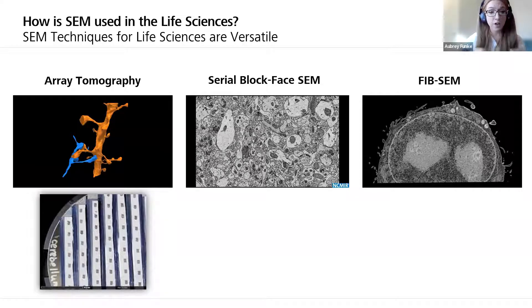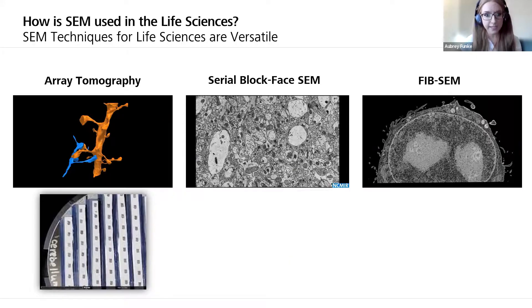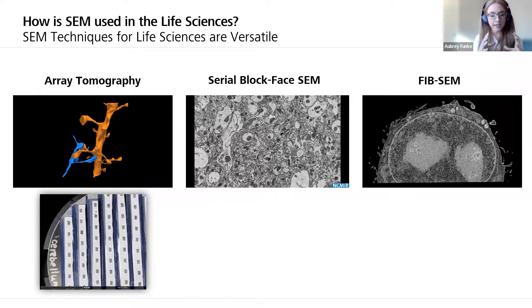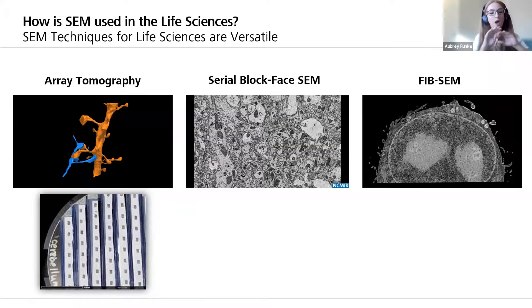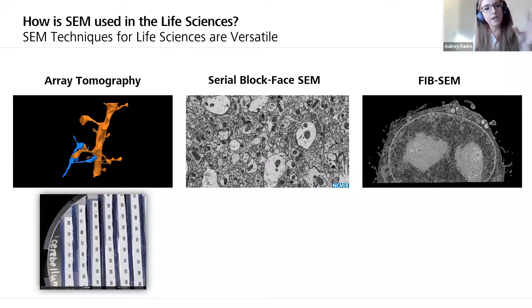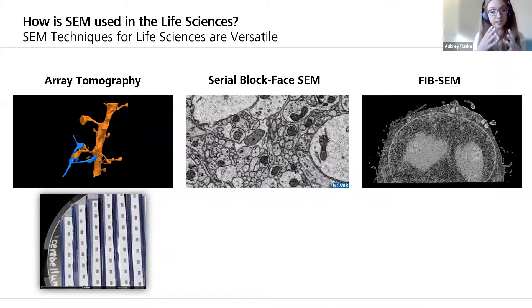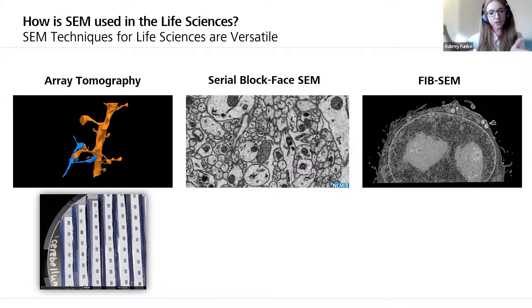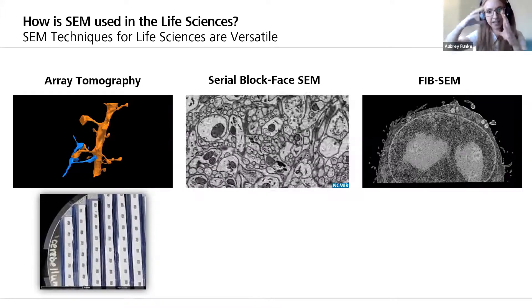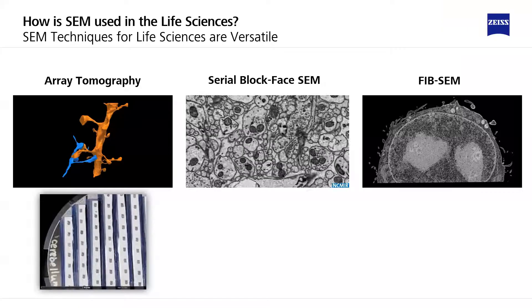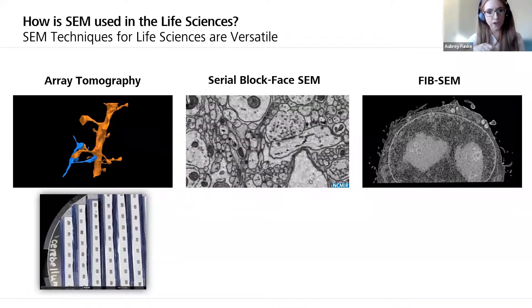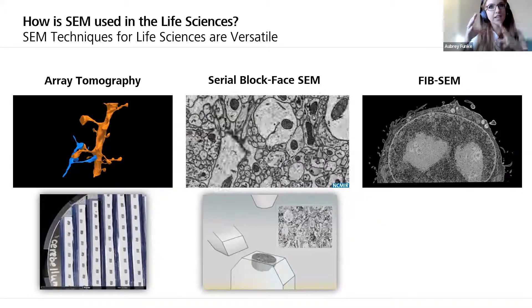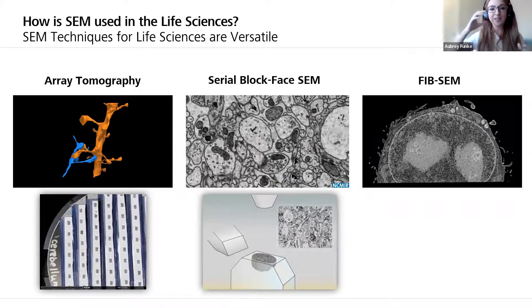Another volume SEM technique is serial block face SEM, or SBF-SEM. This is direct imaging of a sample block that's been resin embedded in some type of epoxy or plastic. The SEM has an in-situ ultra-microtome that takes really thin slices of that sample, then the scanning electron beam scans the surface and gives us an image. We cut away the top, scan the surface, and get an image, doing that over and over to create volume data — saving the time it takes to use the ultra-microtome and collect all those sections separately.